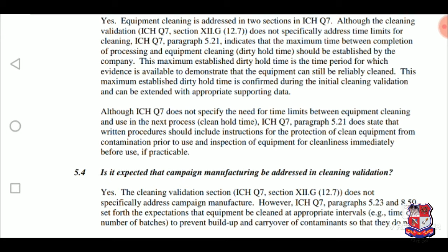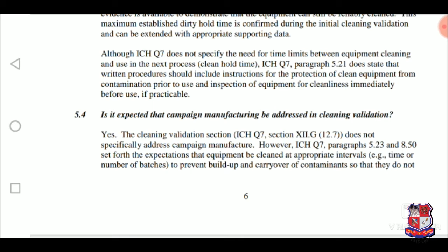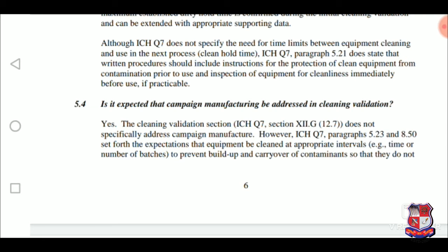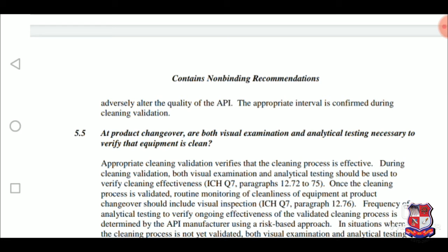Is it expected that campaign manufacturing be addressed in cleaning validation? Yes. The cleaning validation section, ICH Q7 section 12G, does not specifically address campaign manufacture. However, ICH Q7 paragraphs 5.23 and 8.50 set forth the expectation that equipment be cleaned at appropriate intervals, for example, time or number of batches, to prevent buildup and carryover of contaminants so that they do not adversely alter the quality of the API. The appropriate interval is confirmed during cleaning validation.